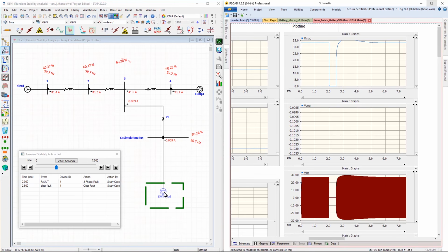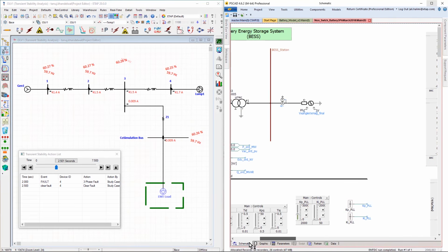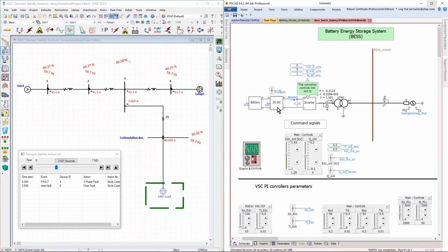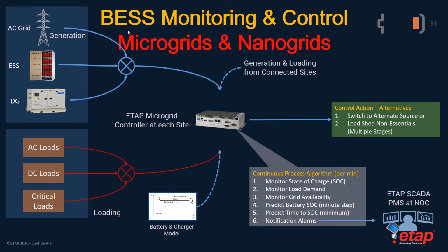So again, in this case, we utilized a battery energy storage model, which can be built inside PSCAD along with the power electronics of the DC to DC converter and the inverter, and solved it together with ETAP in a co-simulation environment. As I mentioned earlier, the BESS models are not only used for design, such as the steady state, short circuits, time domain, dynamic RMS, or dynamic EMT, but they can also be transitioned over to real time.